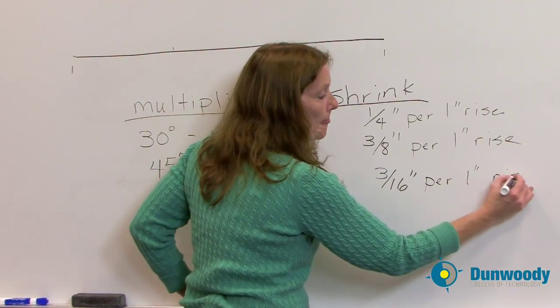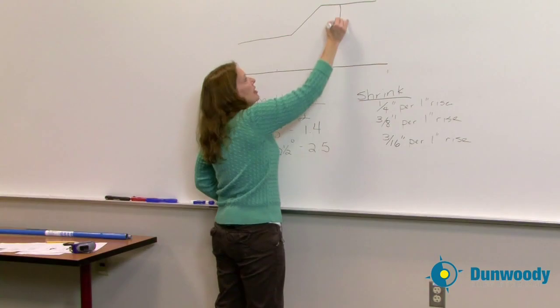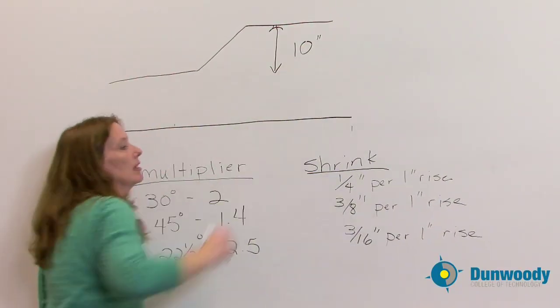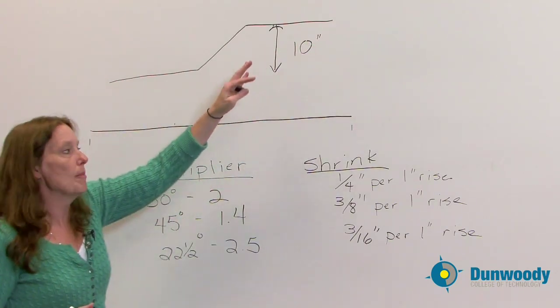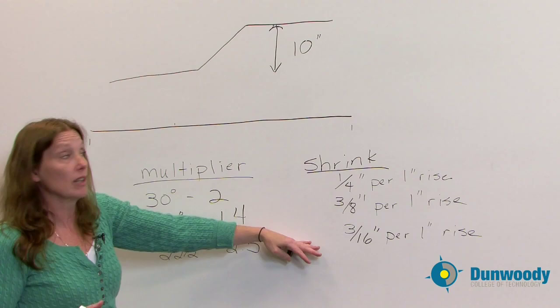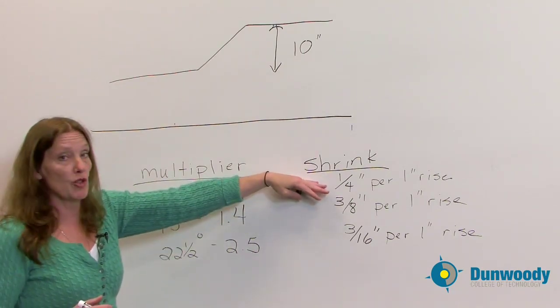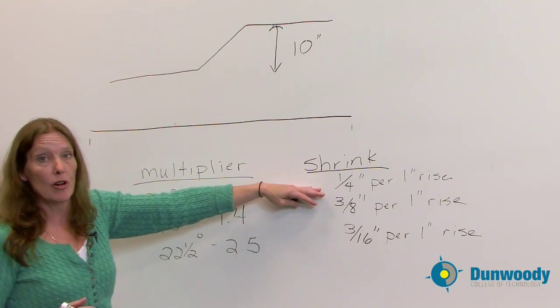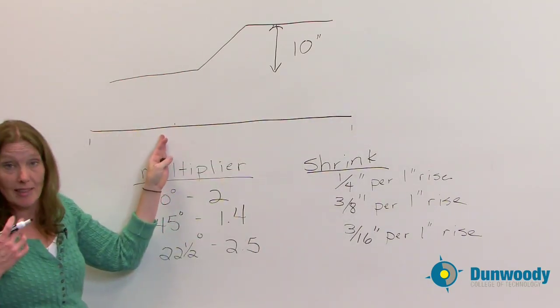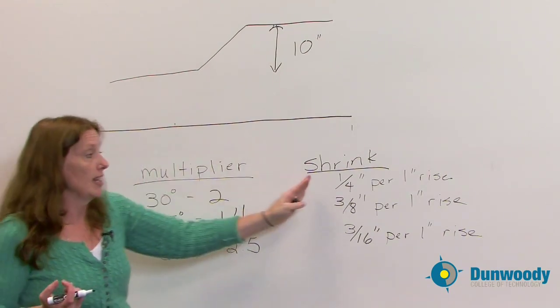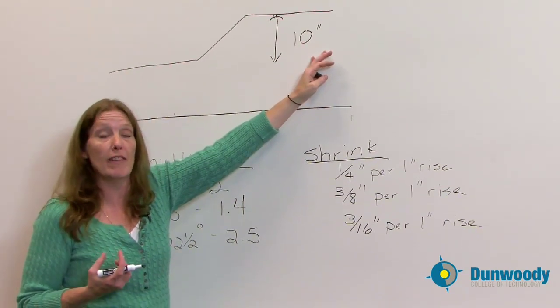So what does that mean? If I have an offset going over a 10-inch obstruction, the overall length is going to shrink up depending upon the degree bend I'm using. In the case of a 10-inch obstruction with a 30-degree bend — quarter inch per inch of rise — I would lose 10 times one-quarter inch, or 2.5 inches of length. So if my obstruction starts at 20 inches, I have to add an additional 2.5 inches to my measurement in order for the bend to come out to the correct value.